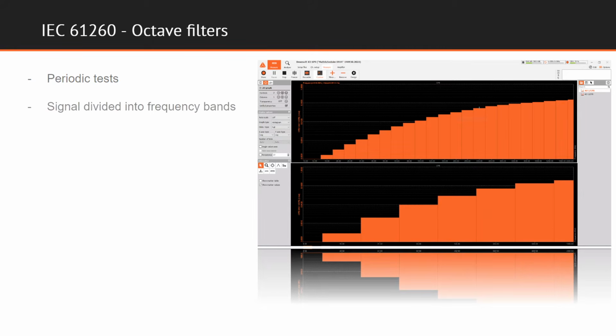IEC 61260. When measuring the spectral contents of sound, the signal is divided into frequency bands with a constant relative bandwidth. Constant relative bandwidth, or shortly CPB, means that the width of the band is proportional to the center frequency of the band. Constant relative bandwidth is most often used in either whole octave or 1/3 octave bands. So these are also the two most often calibrated CPBs.